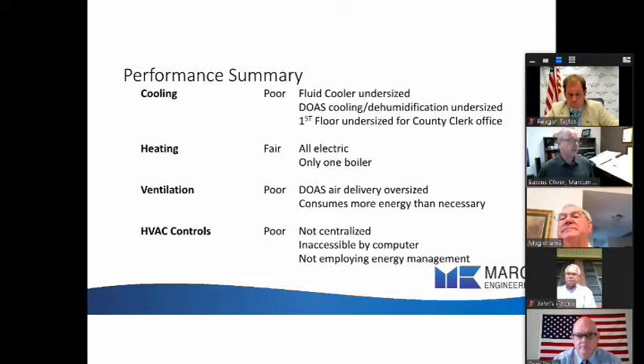Heating is fair, but it's all electric, and we only have one boiler. If that one boiler goes down, we're in an emergency state. You've got to have heating. You can get by without cooling, but you've got to have heat so that you don't freeze the building and burst systems. Ventilation is poor. The DOAS air delivery is oversized, and it's consuming more energy than necessary because it's oversized. And HVAC controls are poor. They're not centralized, they're inaccessible by computer, and they're not employing energy management, which is generally done for buildings of this size. So in my opinion, we're doing poor, fair, poor, and poor.